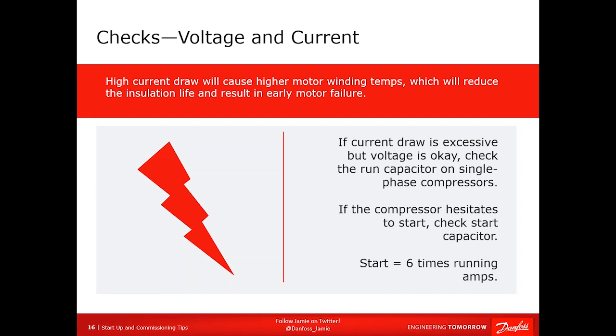Now, power factor should not be a mystery. There are meters today that measure power factor properly. Make sure you measure it. But remember, above all, the compressor and the fans, for that matter, should not hesitate when they start. It should come up to speed immediately.